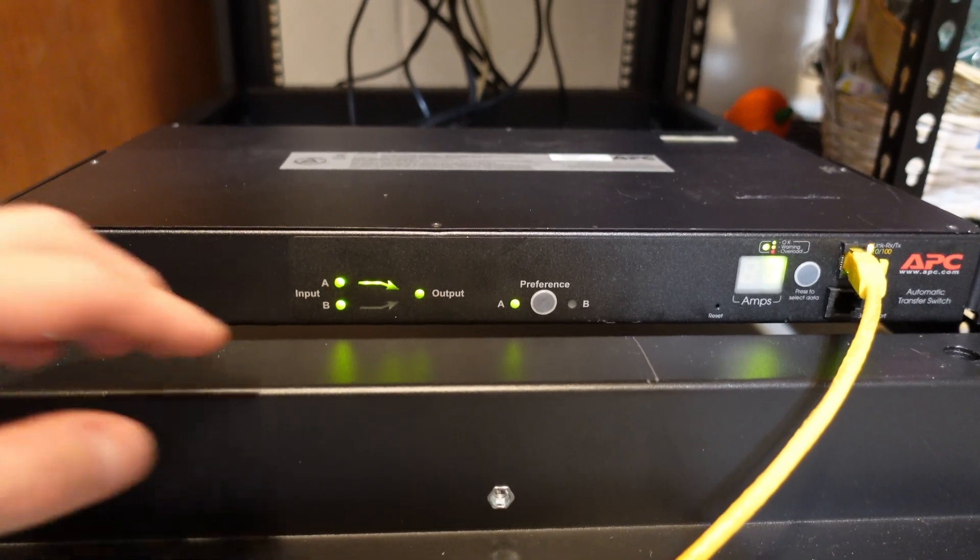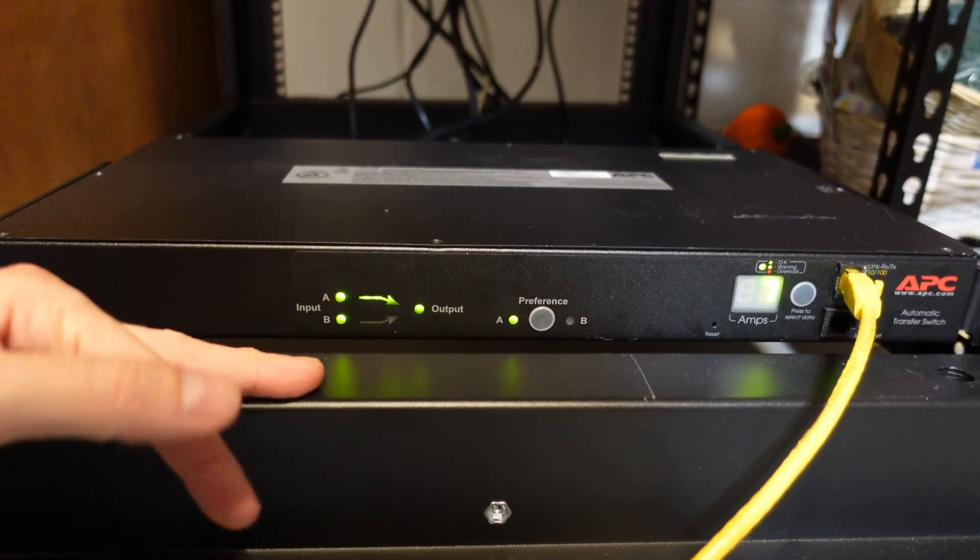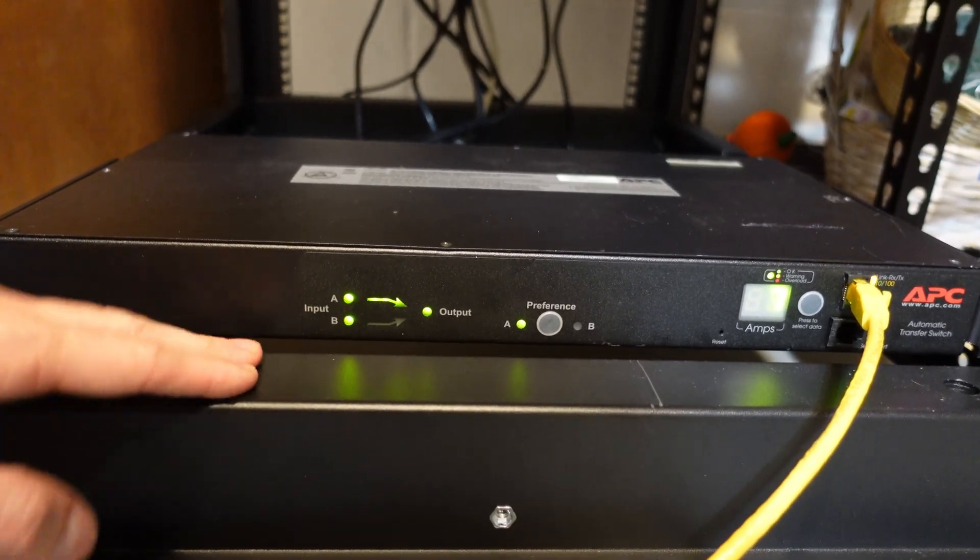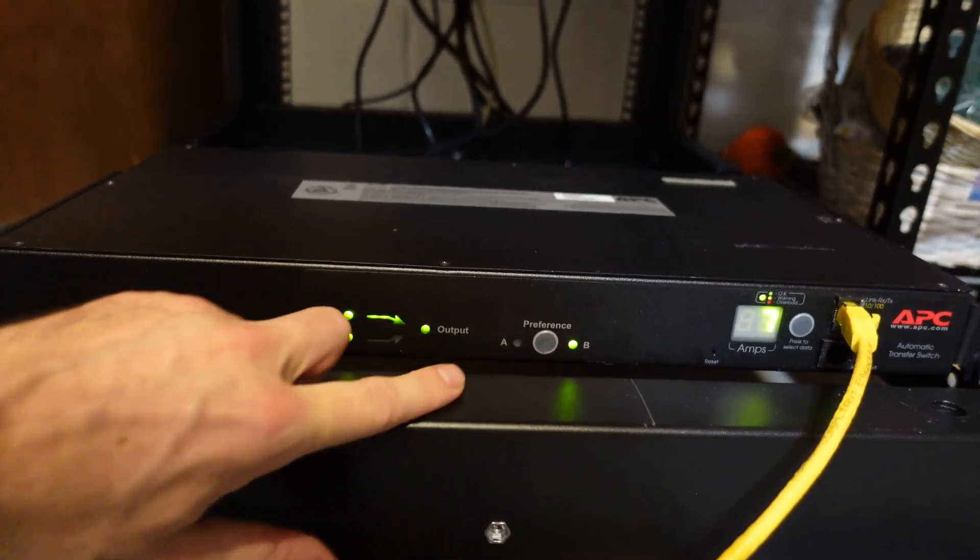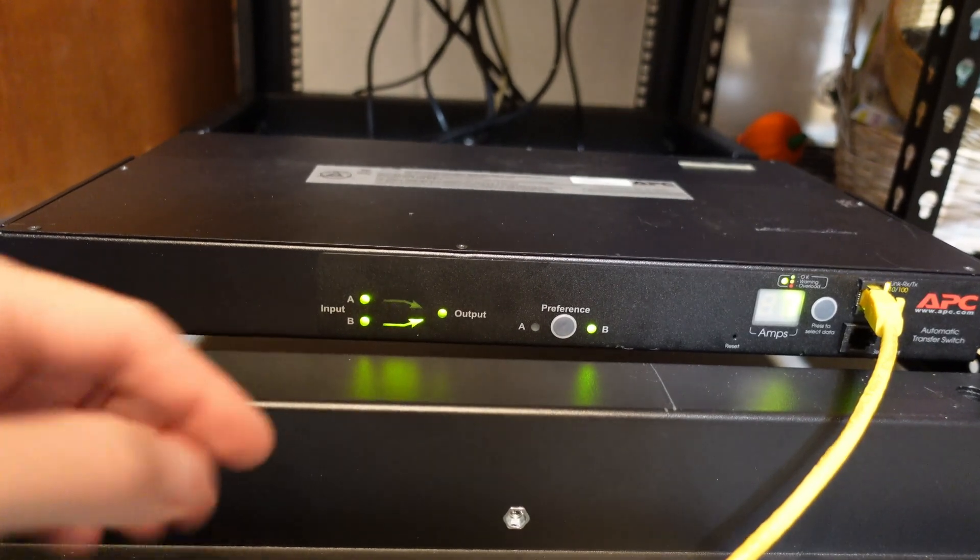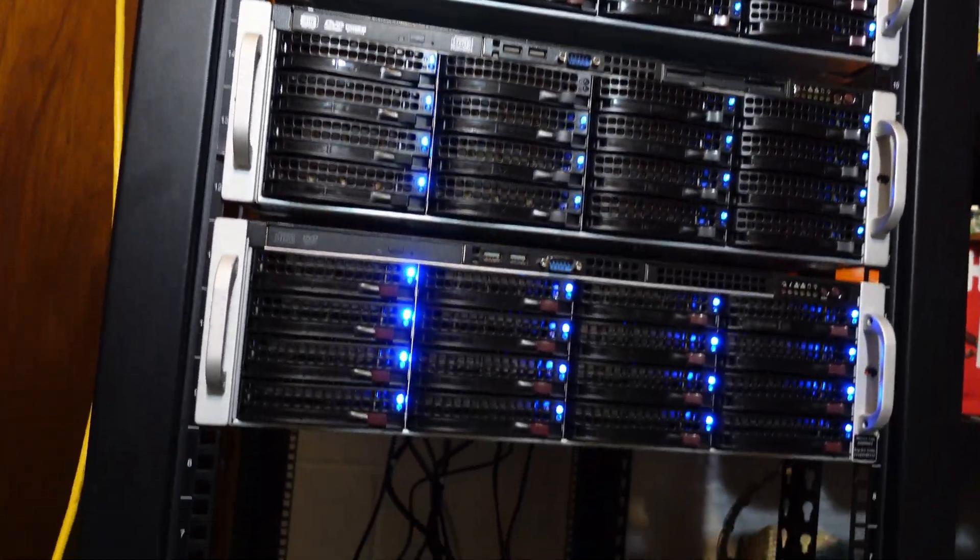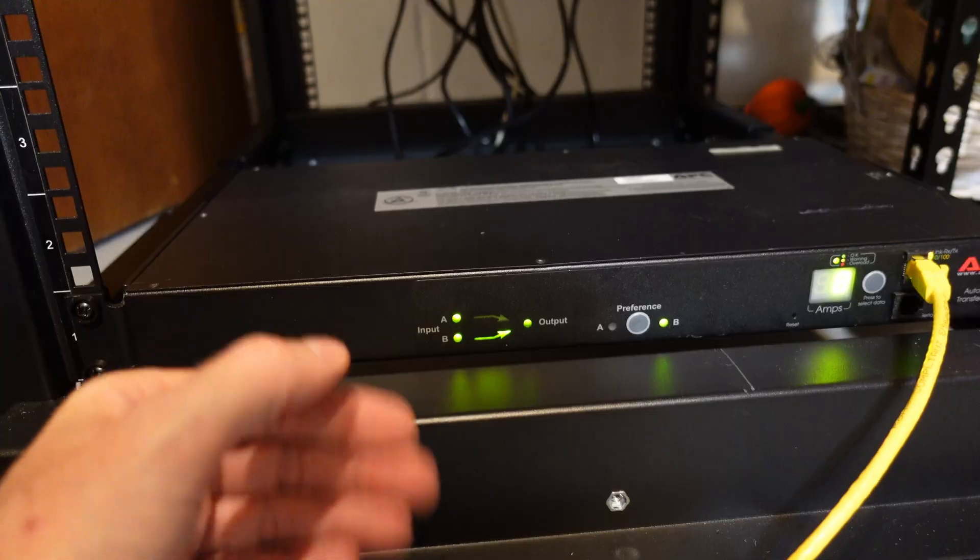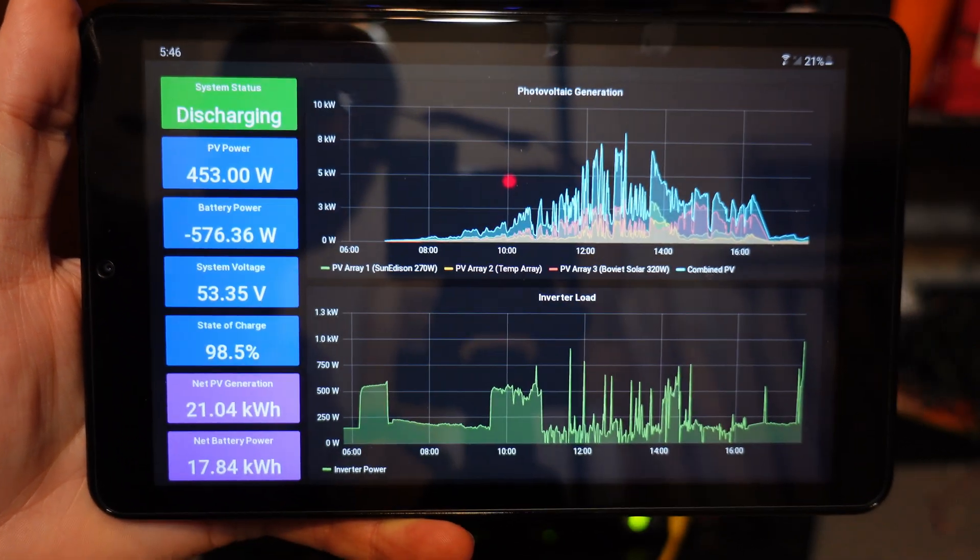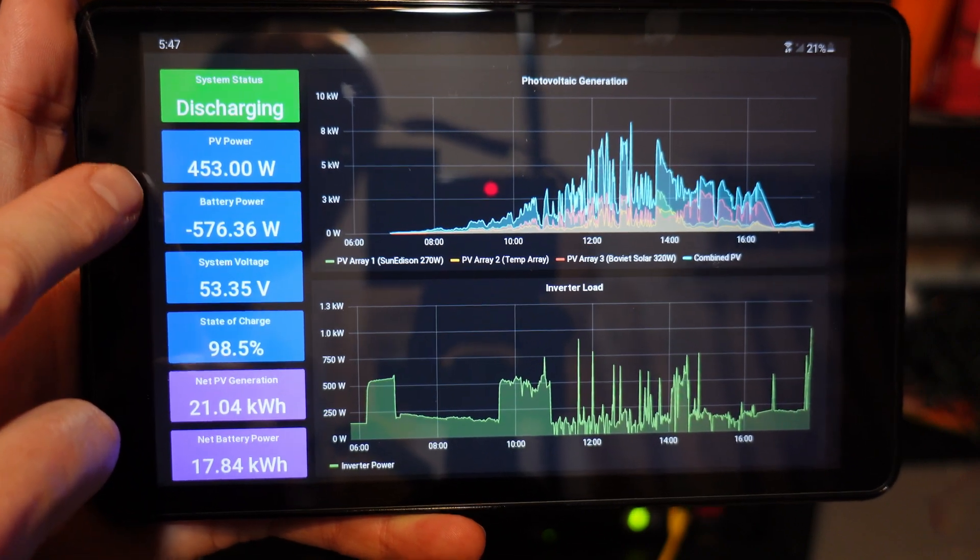And this is where it gets super cool here. So let's say it's a bright sunny day, my 60 kilowatt hour battery is full and I have excess energy, which does happen a lot during the summer. So all I need to do is simply come down here and press this preference button to B. Wait approximately a minute - oh, it was pretty quick - and you can see it switched to source B. So now this entire rack is being powered by completely off-grid power with the press of a simple button. And how do I know it's actually working? Because now I can come over here to my solar display for my solar system and I can see I'm pulling approximately a 1000 watt load here between these two figures, and I can see the load spiking here on the bottom right.